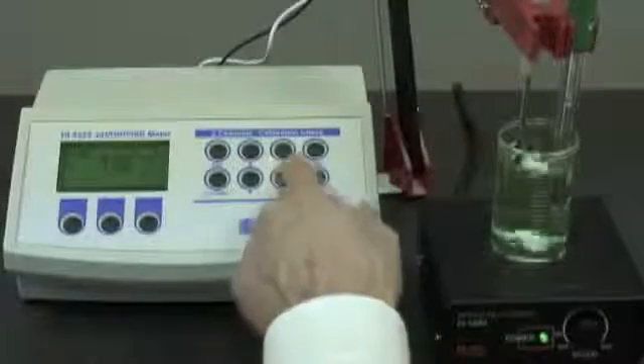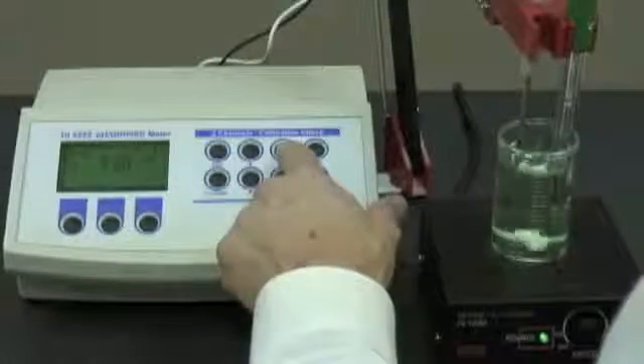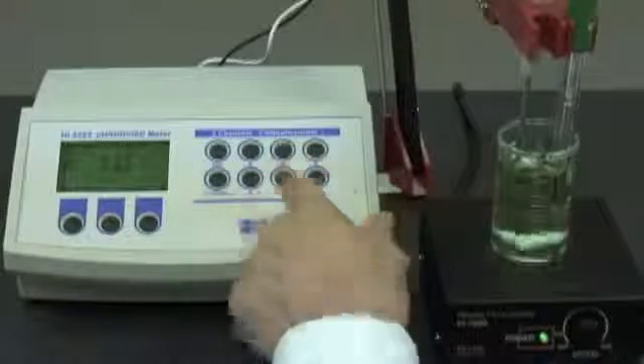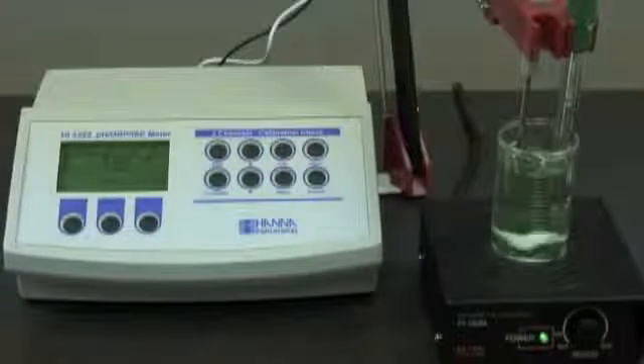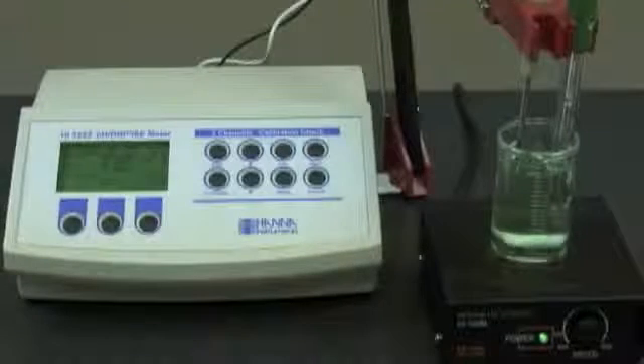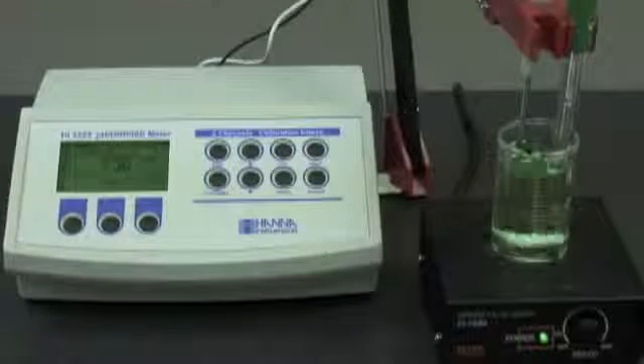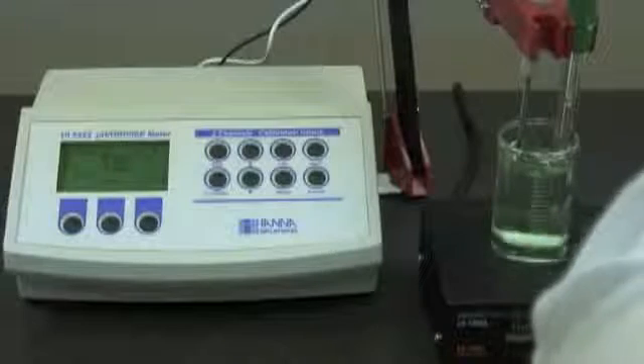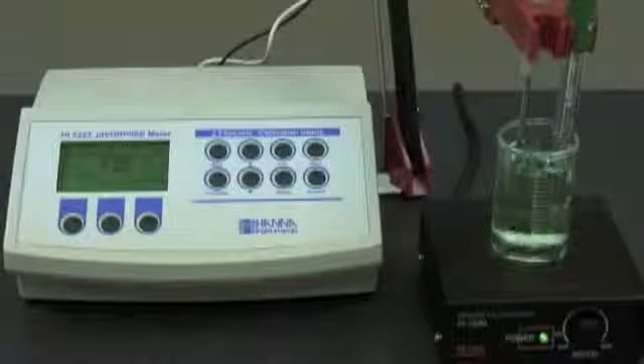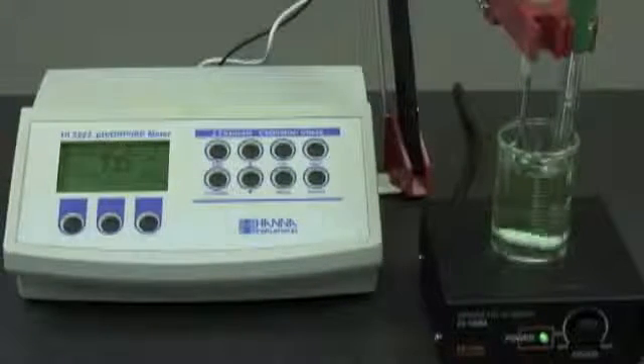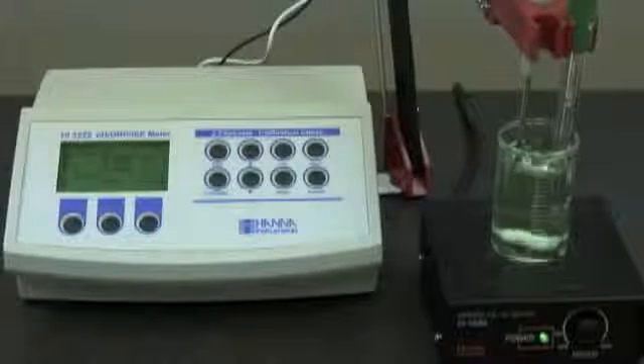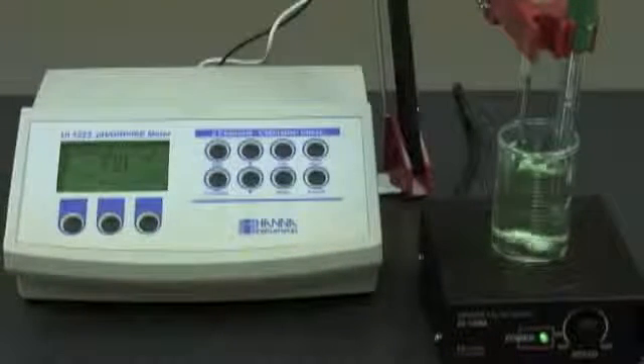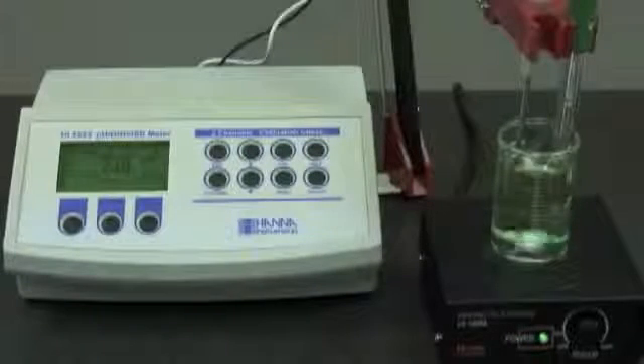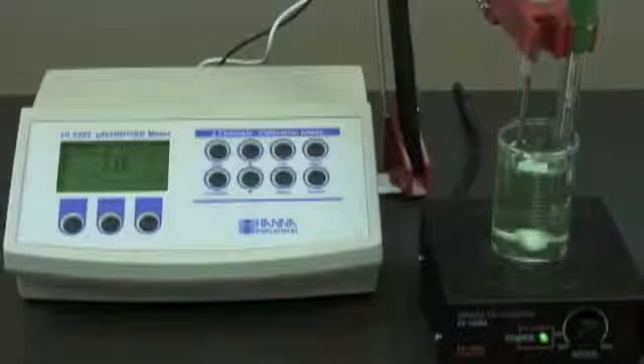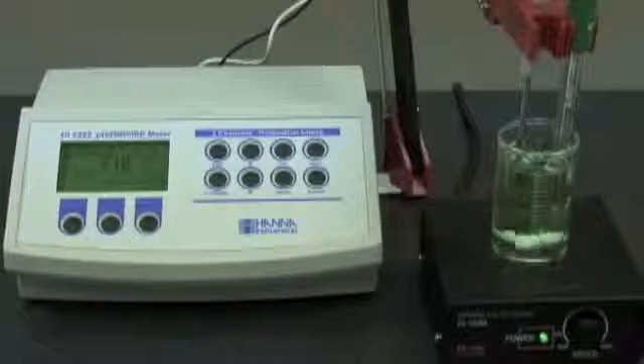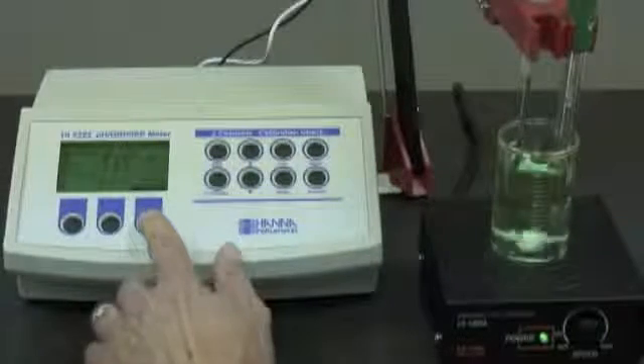Alright, I'm going to start by hitting the cal button. And keep in mind too, it's important to make sure that your junction is covered by the solution, otherwise the calibration is not going to work. So what I've done here is, again, I pushed the cal button and I'm waiting for the meter to read 7.01 or to recognize that buffer. And when it does, I'm going to hit the confirm button. So let's give that a second to come up. Okay, so I'm going to hit the confirm button.